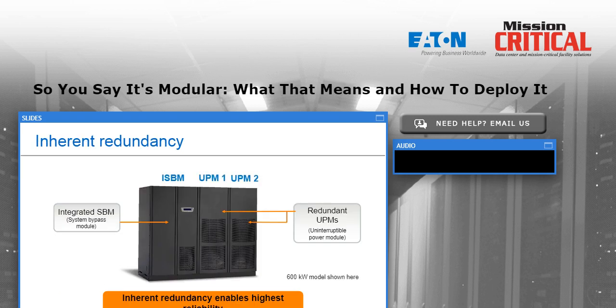The inherent redundancy we talked about is shown here. This particular UPS has a section about the size of a refrigerator on the left called an Integrated System Bypass Module, or ISBM. This is where the terminations are made, where the static switch is located, and the communications in the front panel. But on the right-hand half of the machine, there are two what we call UPMs, and each one of these is identical to the other. They're 300 kilowatts each, and they basically provide an N+1 redundant or capacity parallel system. Now, this machine is all built on one base, so it installs like one big UPS. It moves around like one big UPS as I'm doing that installation, but functionally it's a two-module parallel system.